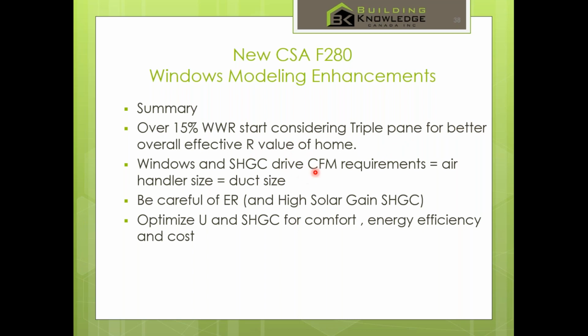So windows are important. Solar heat gain, that number is not only going to drive the cooling load, but your cooling load will drive your CFM requirements and the fan size, which in effect drives your furnace or air handler size, which then drives your duct size. So, be careful of high ER. And again, optimize U value and solar heat gain. We would say ignore ER, even though it's a code compliant number, and going forward, start to look at U and good solar heat gain numbers as a whole.